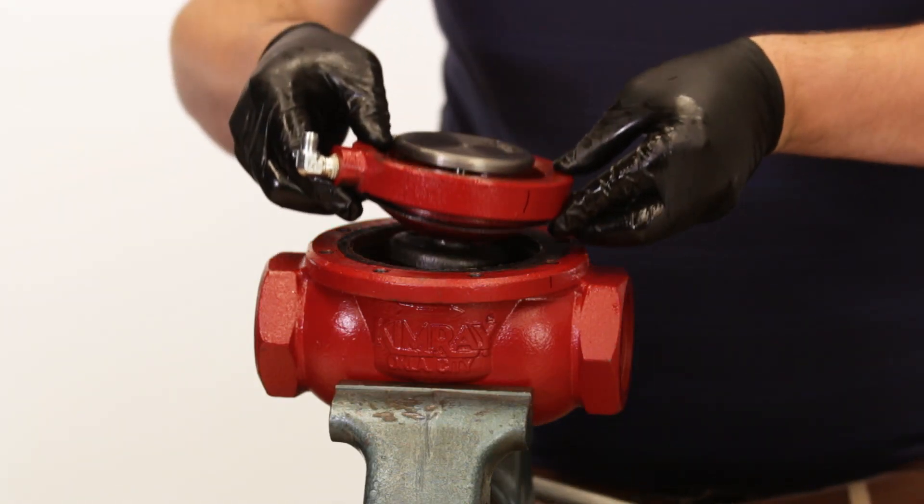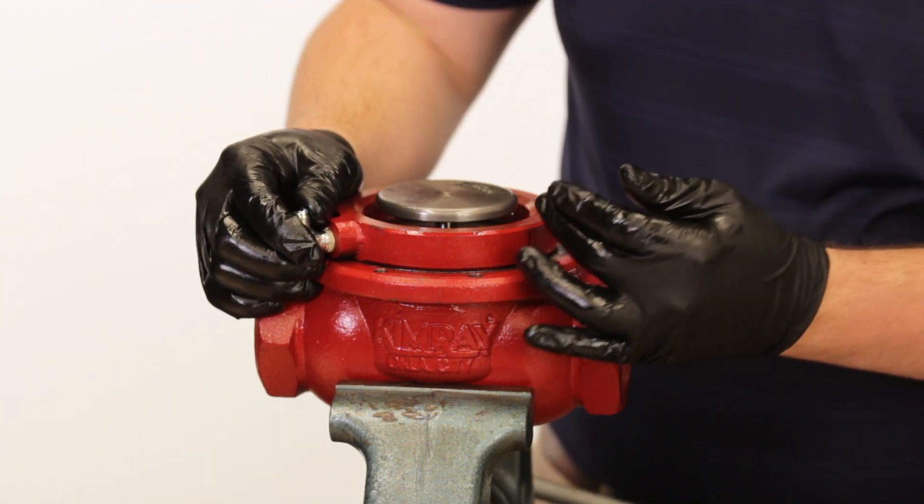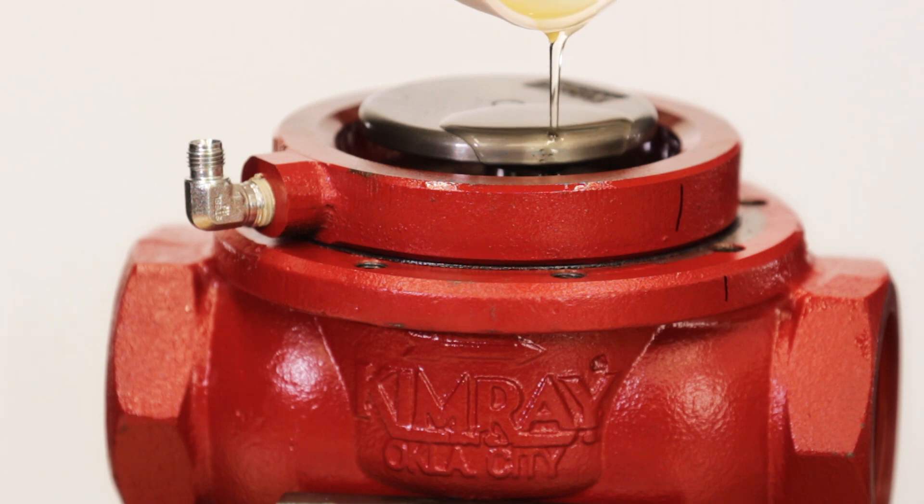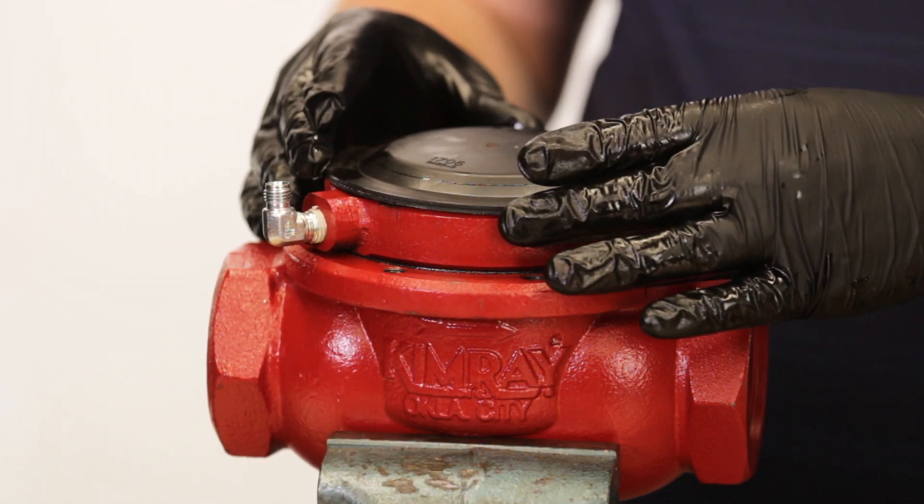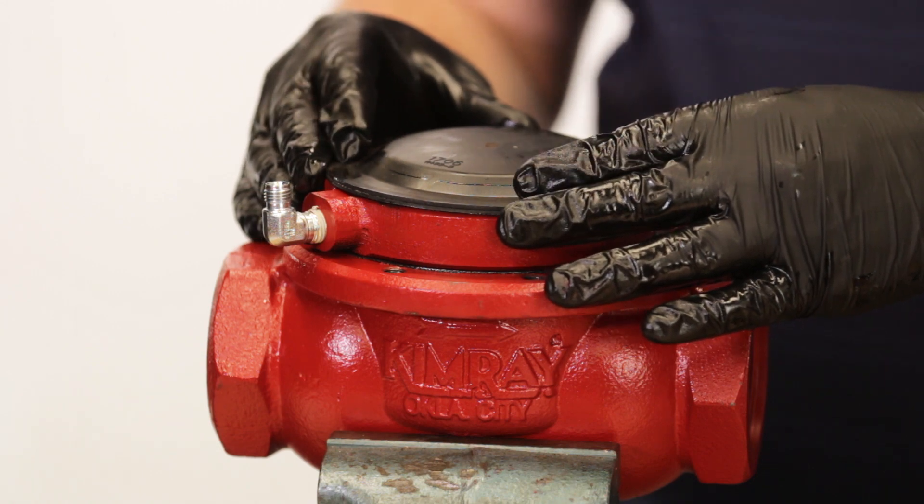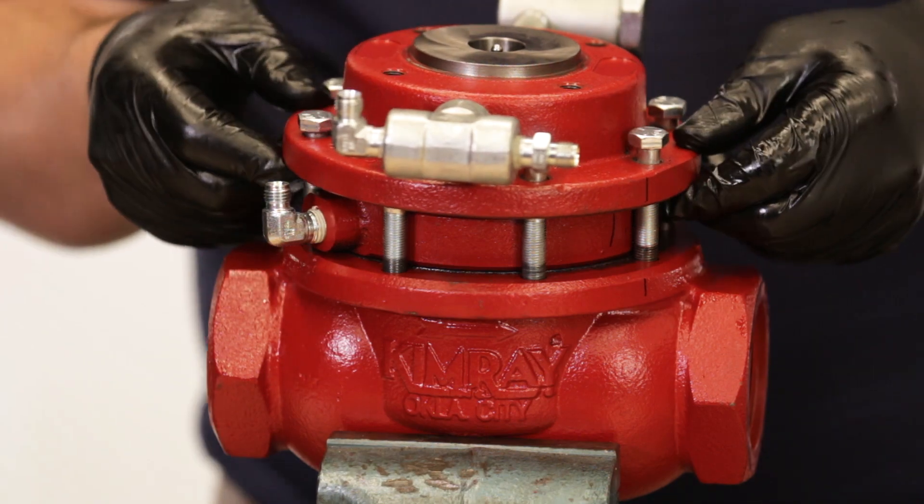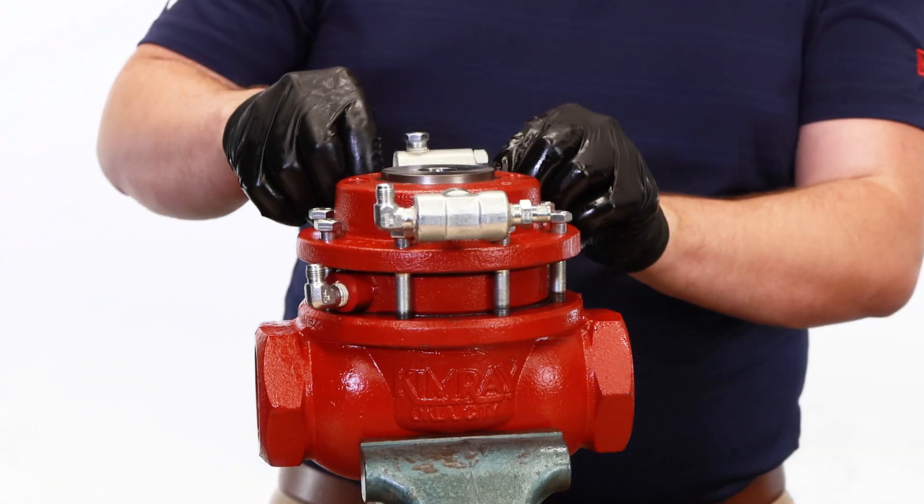Put the body back in the vise and put the lower housing back on the body. Be sure to align your marks. Fill the lower housing or oil bowl with low gravity oil, enough to cover the communication hole. Place the diaphragm on top, bevel side facing up. Replace the upper housing, aligning your marks. Only hand tighten the bolts at this point so that it is easier to replace the tubing later.